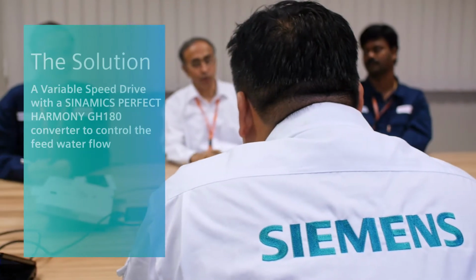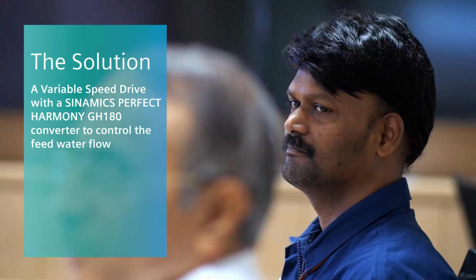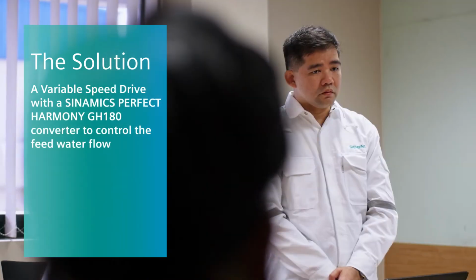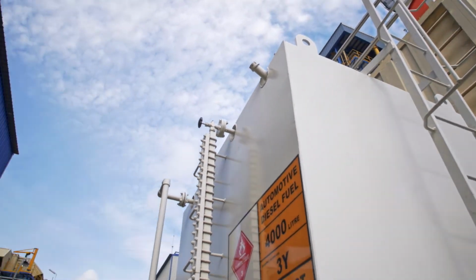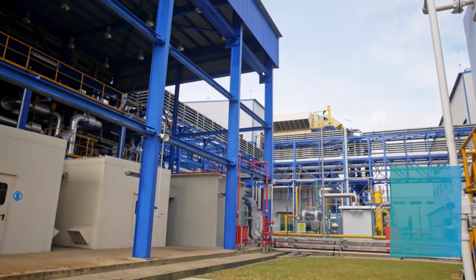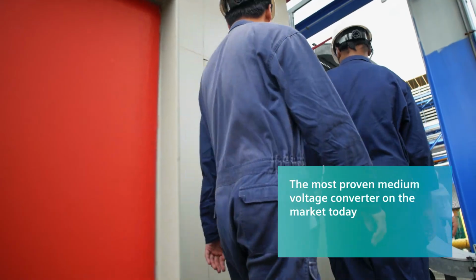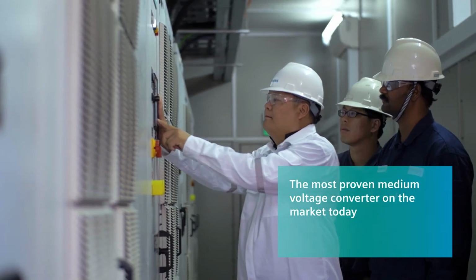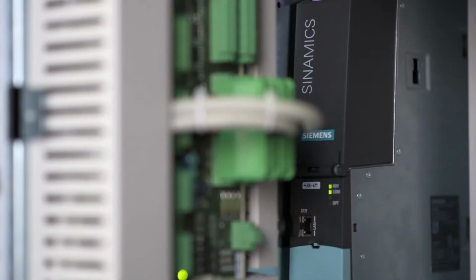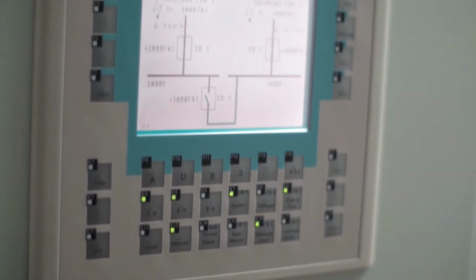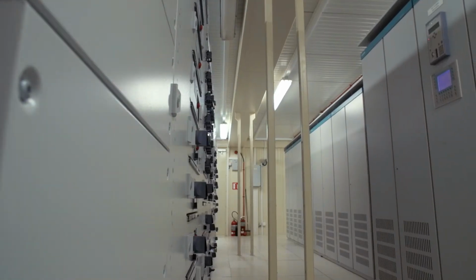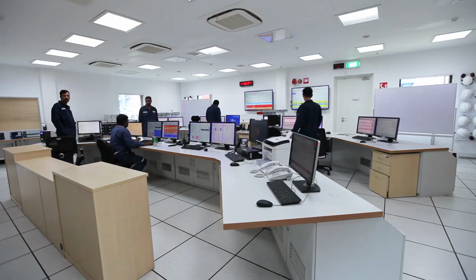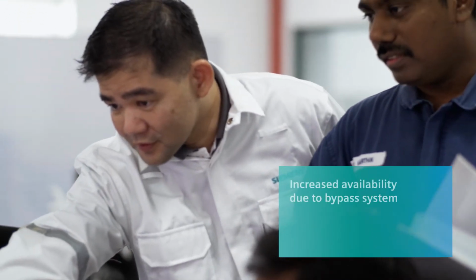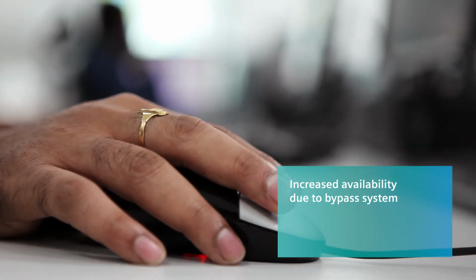Siemens was awarded to continuously restore performance degradation at the power plant at applications like, for example, the HRSG's feed water system. The SINAMICS PERFECT HARMONY GH180 converter system is the most proven medium voltage converter on the market today. Its design features an integrated transformer and the ability to scale the drive for a wide range of voltage and output power. The drive offers increased availability due to its modular design and ability to bypass any one cell during operation.